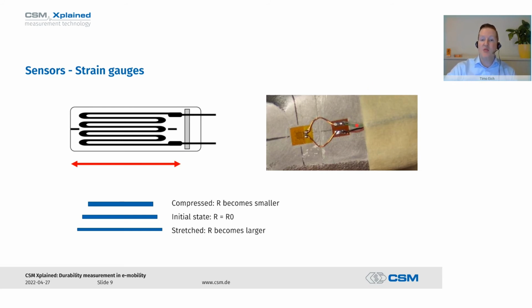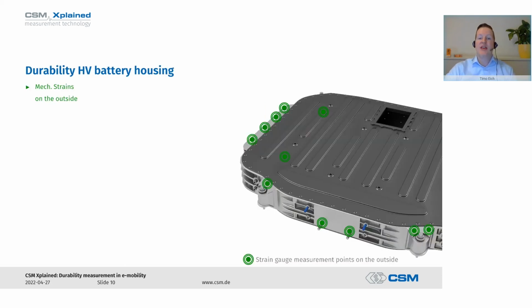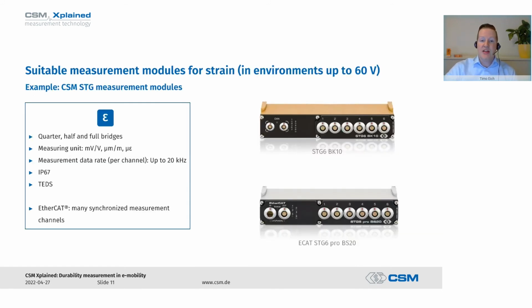And on the right picture here, we see an applied strain gauge, in our case, one with a strain relieved cable connection pad. With such strain gauges, we can now measure strain on the outside of the HV battery housing. And for this, of course, we also need a suitable measuring amplifier which supports Wheatstone measuring bridges. So for environments up to 60 volts, CSM offers measurement modules for different bus systems. The upper picture here shows the CAN bus variant, a module providing 6 channels for quarter, half, and full bridges and slower sampling rates. And the picture below shows the EtherCAT-based module, also with 6 channels and fully synchronized acquisition with up to 20 kHz sampling rate per channel.